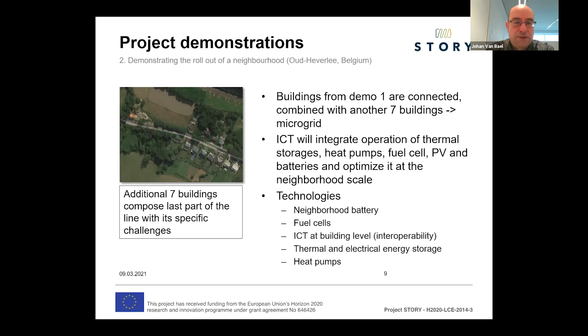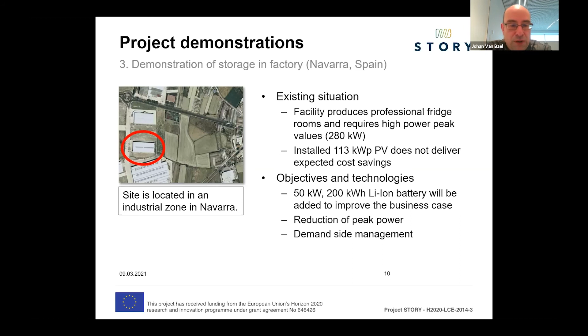The next demonstration project is in the south of Europe, in Spain, where an industrial facility has a lot of PV installed on the roof. They wanted to increase self-consumption of this PV, since at this moment it was not fully self-consumed, so they installed a battery. The technical specifications are 50 kilowatts power and 200 kilowatt-hours of energy storage capacity, in order to reduce peak power and increase self-consumption of PV.